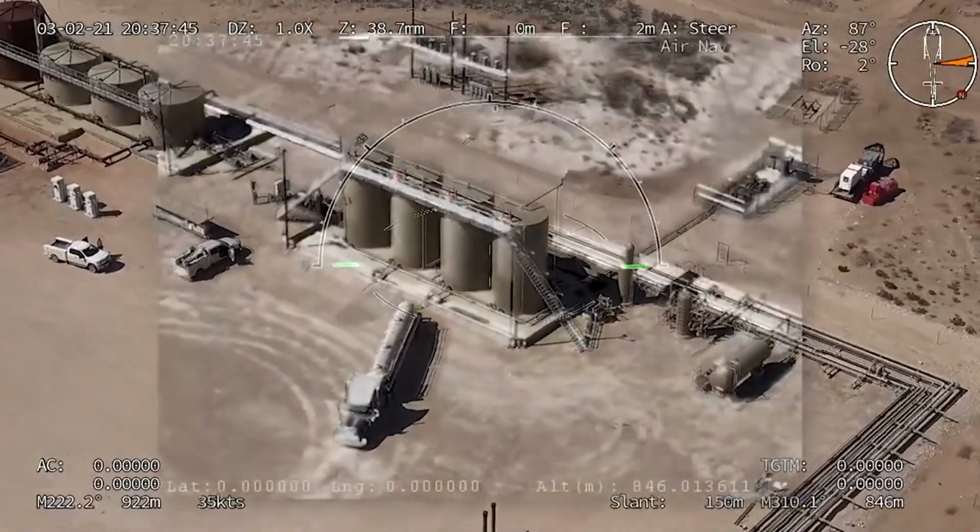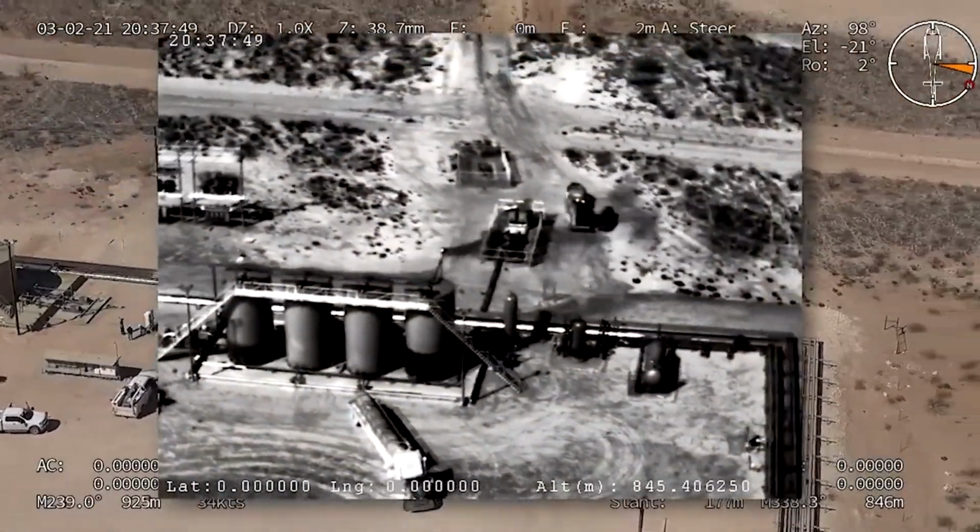That's a little over 500 grams. Part of my background is that I was originally involved in the first optical gas imaging camera, developed from about 1999 to about 2003. There we started off with a 320 by 240 resolution, known as quarter VGA. That was the standard for almost 20 years, until we introduced a VGA resolution, or 640 by 512. The benefit is about 4 times as many pixels, so you're putting more pixels on target, giving higher resolution and making it easier to see gas leaks, either smaller ones or from farther distances.